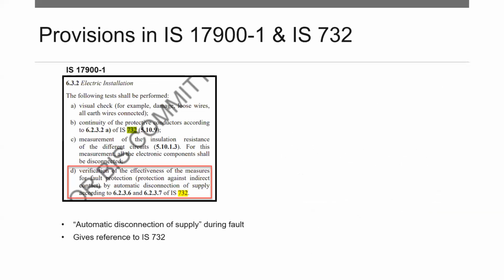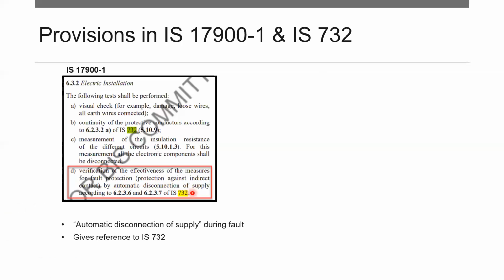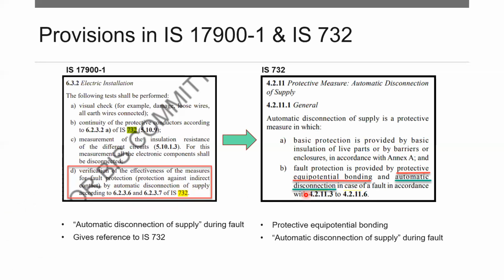Now, last year in December 2022, 17900-1 has been published, and IS 14665 and 17900-1 and 2 are both concurrently running till the IS 14665 is withdrawn. Now, the background is this code has been adopted from ISO 8100-1 and 2, which comes originally from the 81-20 and 81-50 requirements. And this code is now talking about the automatic disconnection of the supply, and also gives a reference to the IS 732, 6236 and 6237 clauses. We'll see on the slide here.